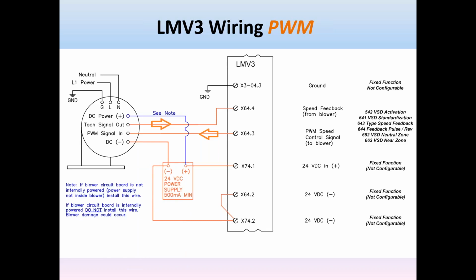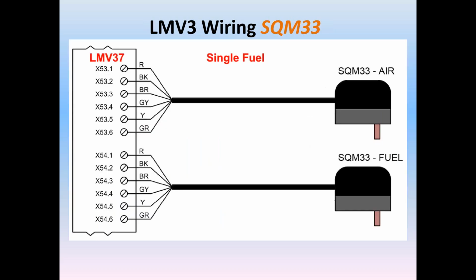Some PWM motors need power to the control board inside the PWM. If that's true, then that blue wire, you see the note, then you would provide power to the board inside the PWM as well. Some motors need it, some don't. It depends on which motor you select. If you're doing a single fuel LMV37, then the air servo, the SQM33 air actuator, and the SQM33 fuel actuator would be connected to the LMV37. Air would go to X53, fuel would have to be plugged into X54.